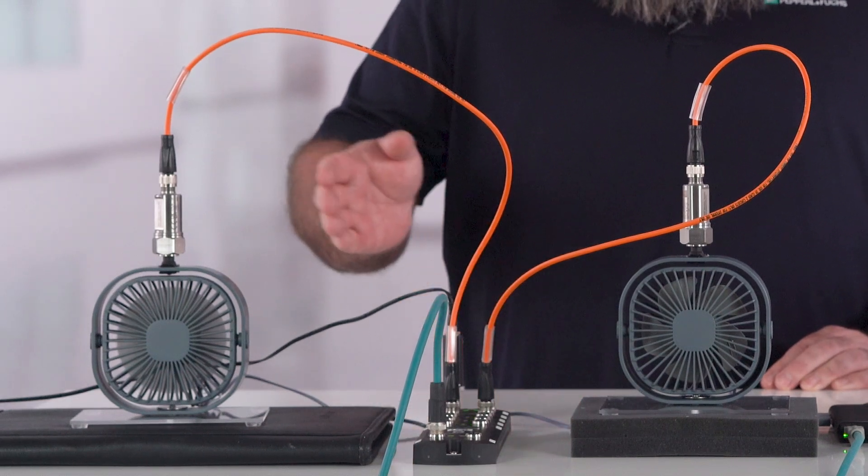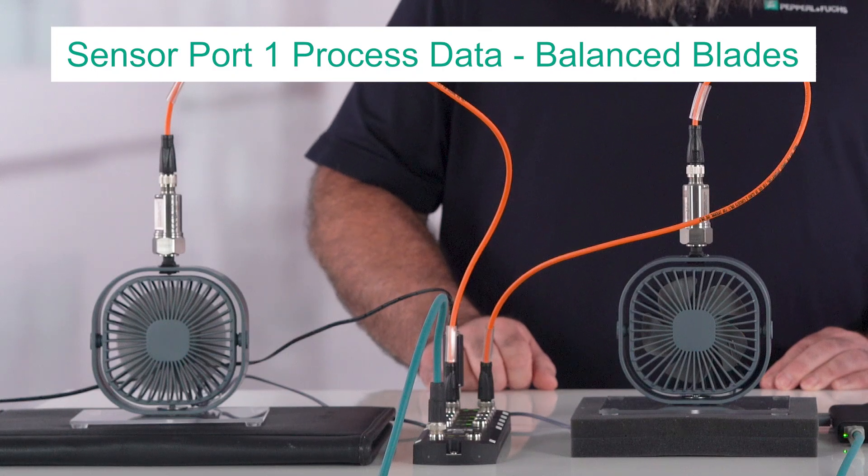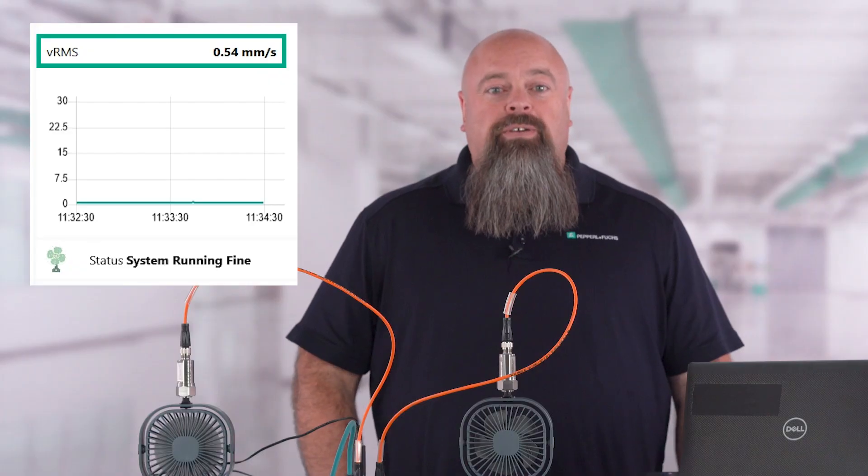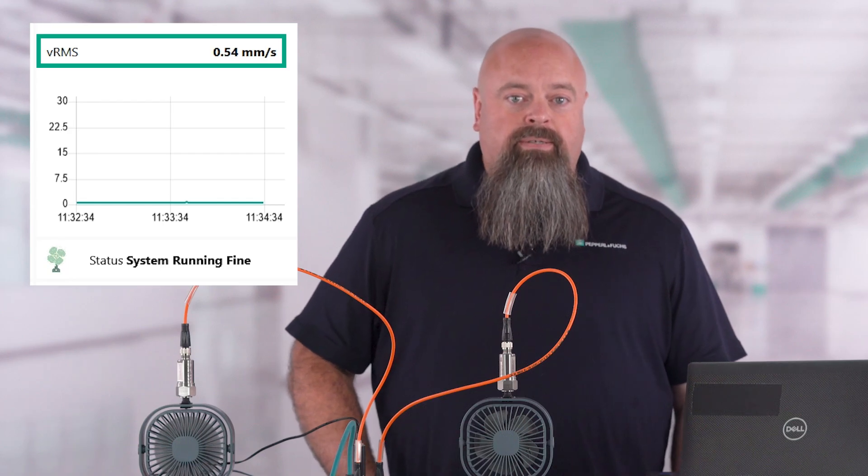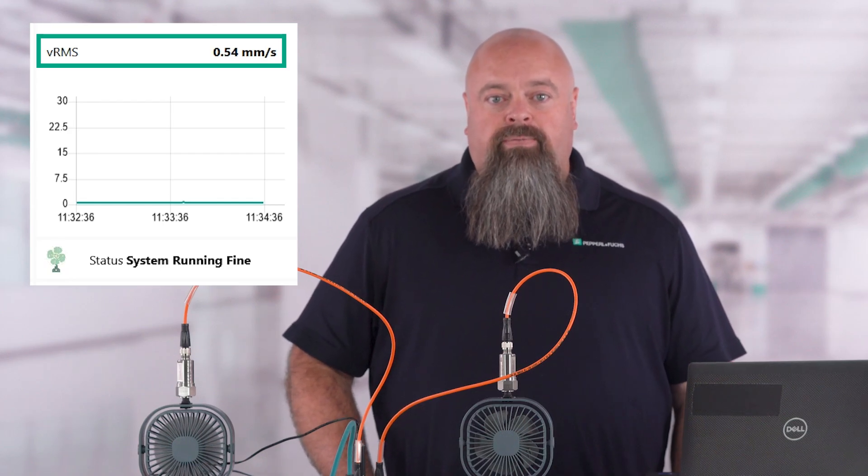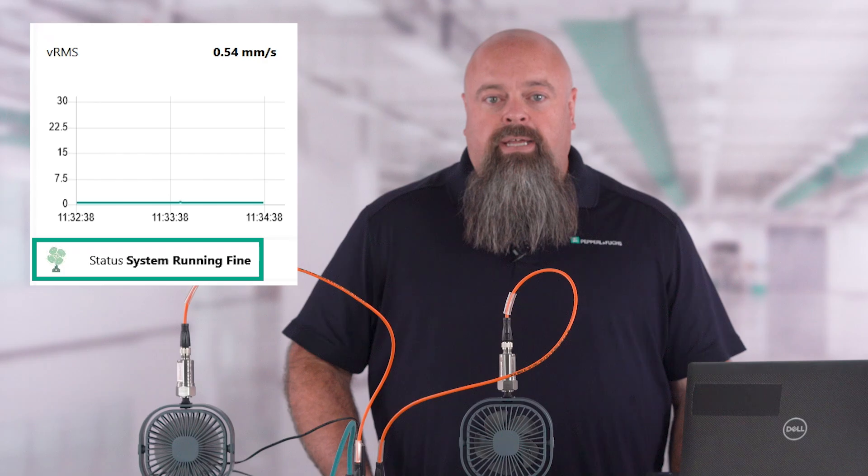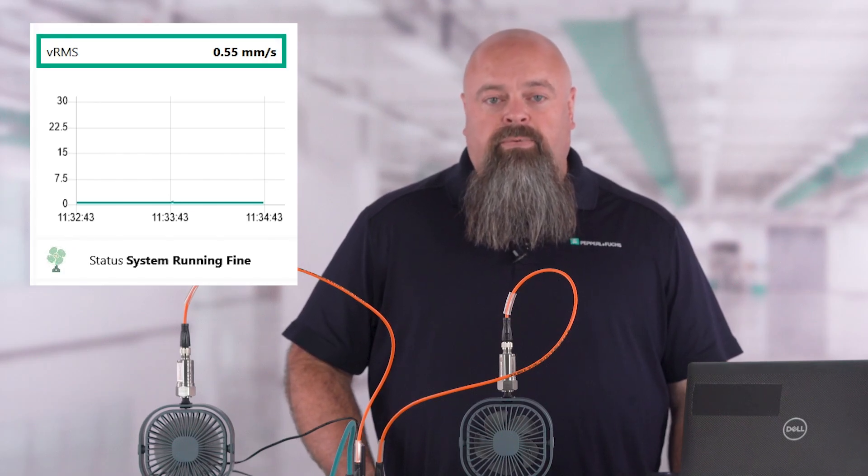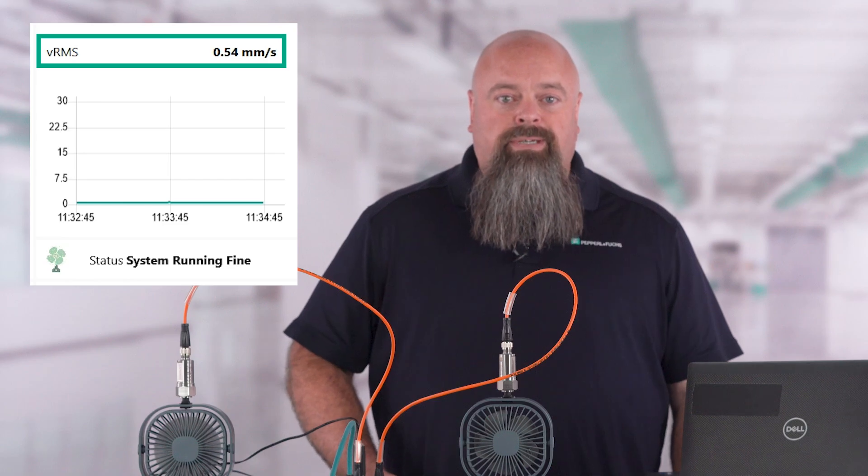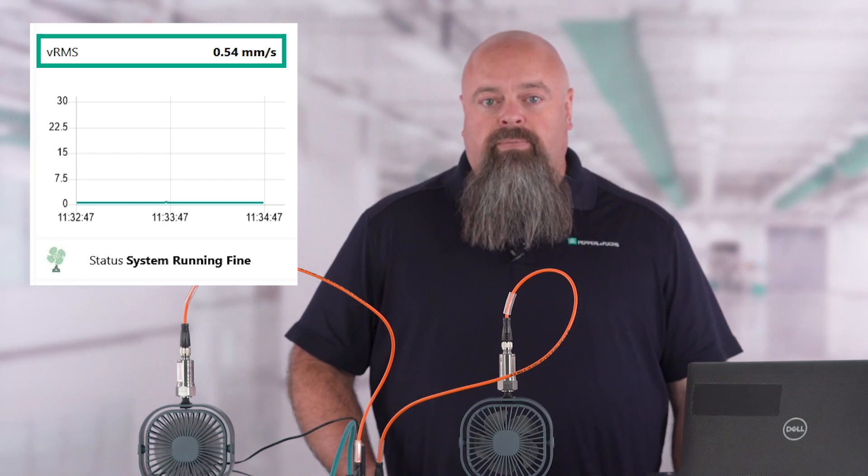The fan on the left is running, represented by the top line labeled Sensor Port 1 for balanced blades. You can see it has regular vibration with an RMS velocity or VRMS holding steady around 0.55 millimeters per second, and the fan icon indicates the system is running fine. In this example, the customer would use this value to represent a normal vibration for a balanced fan.